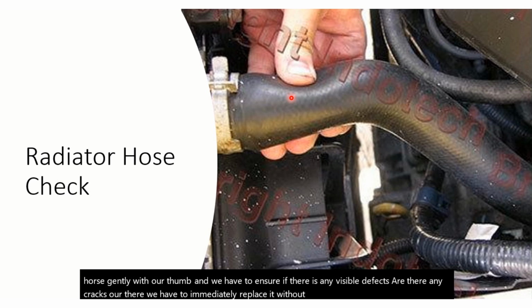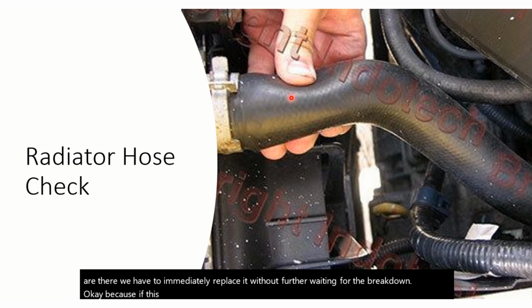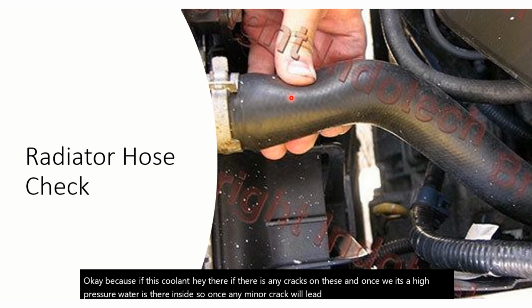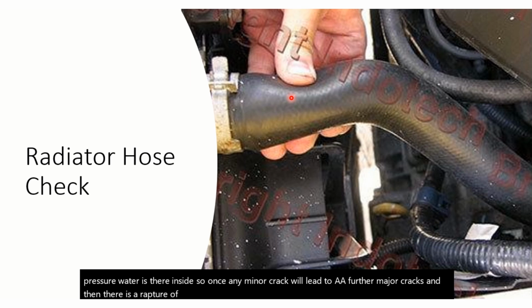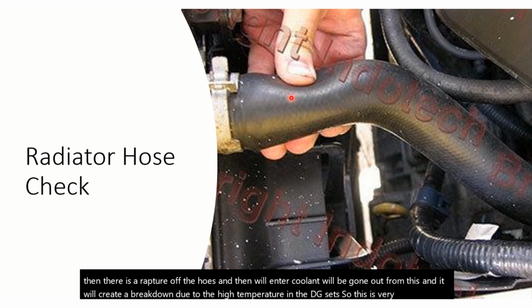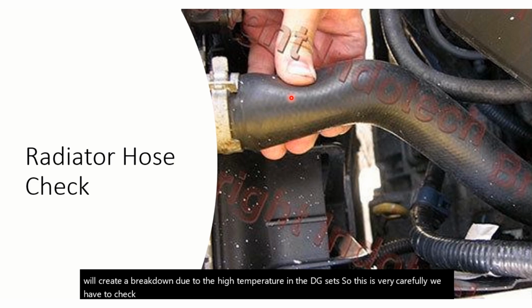for the breakdown. Because if there are any cracks on these and there is high pressure water inside, any minor crack will lead to further major cracks, and then there is a rupture of the hose, and the entire coolant will go out from this, and it will create a breakdown due to high temperature in the DG sets. So we have to check this very carefully, and at every B check it has to be replaced.